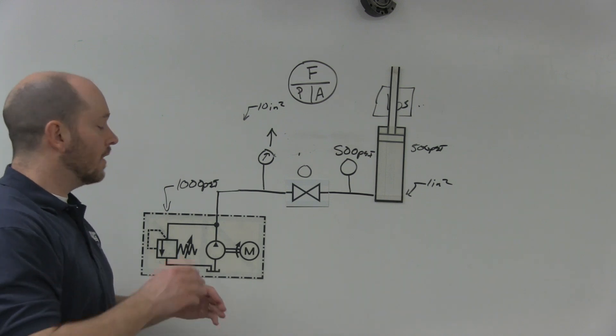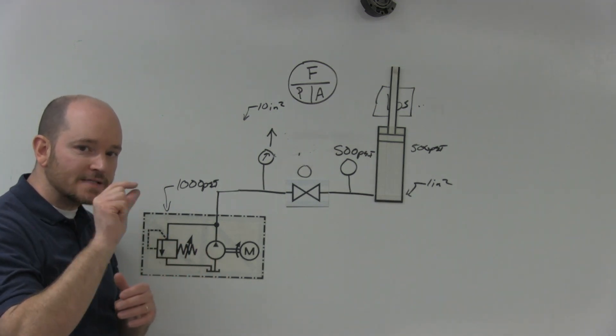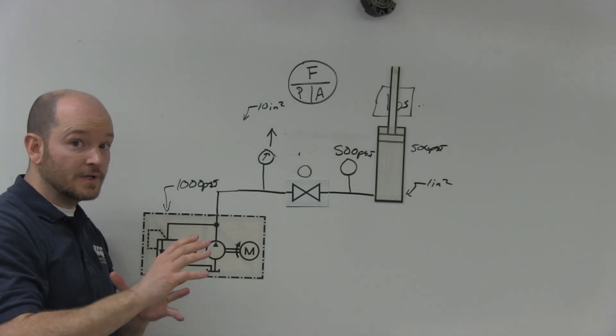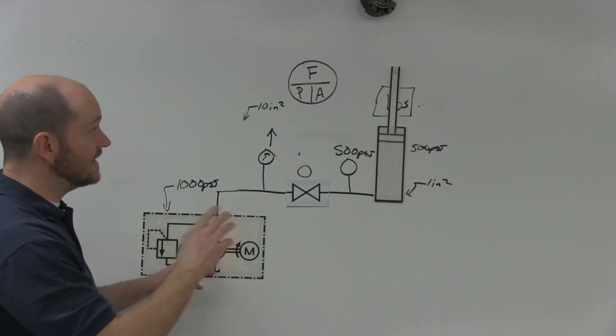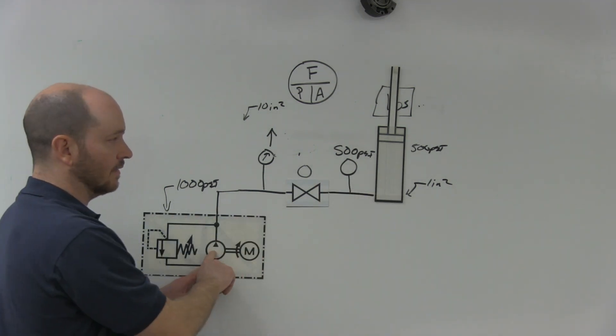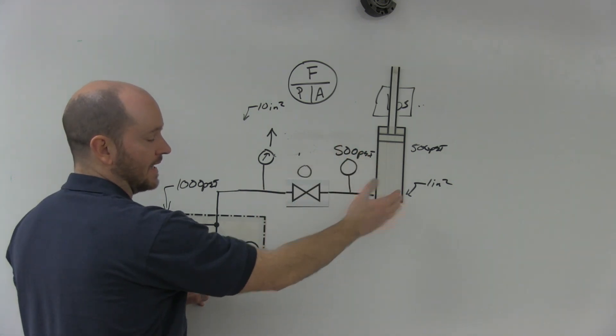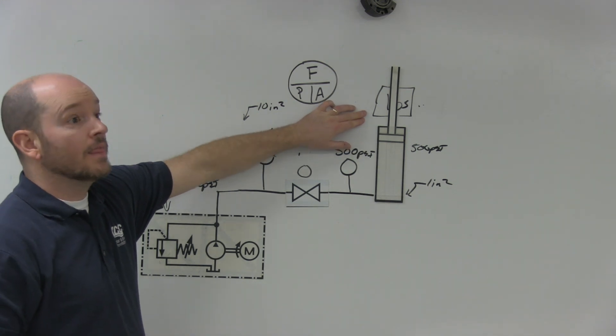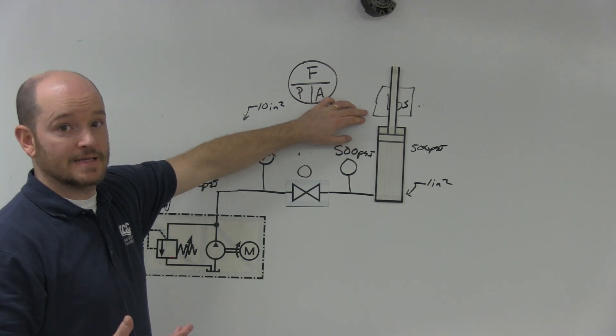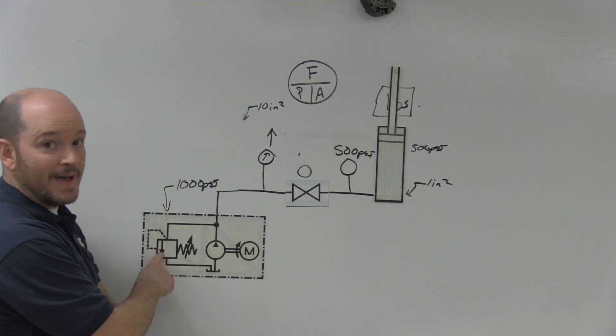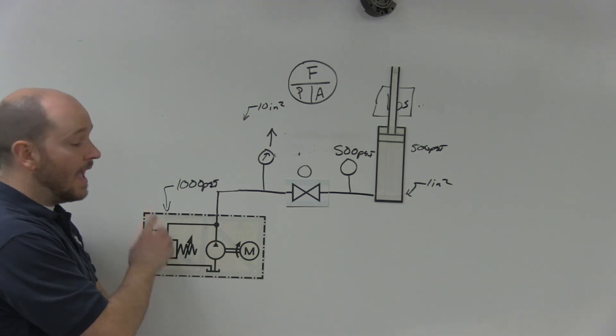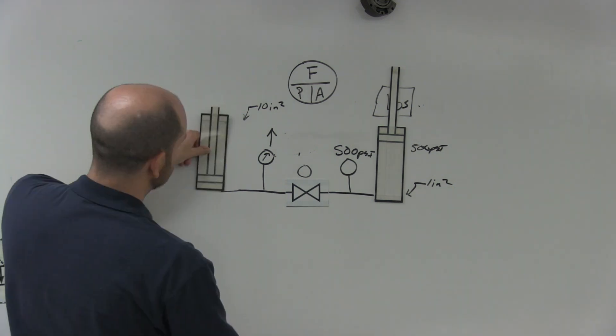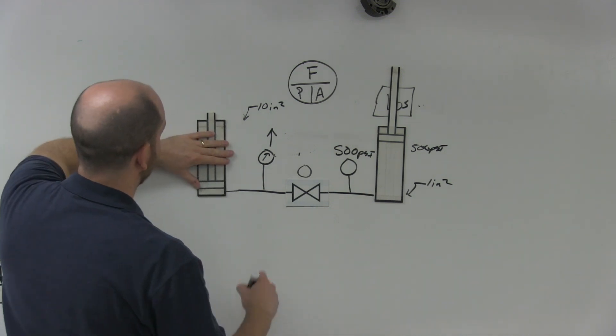Remember, a pump's job is to create just enough pressure to create flow. This is really important: if the load takes 400 PSI, it will only create 400 PSI; if it takes 200 PSI, only 200 PSI. But if the load required 1,500 PSI, it would never move because the relief valve is the path of least resistance — that's why the pressure relief valve is so important.